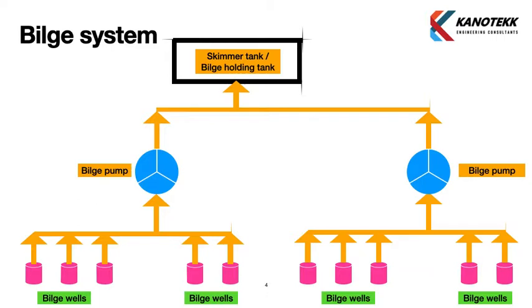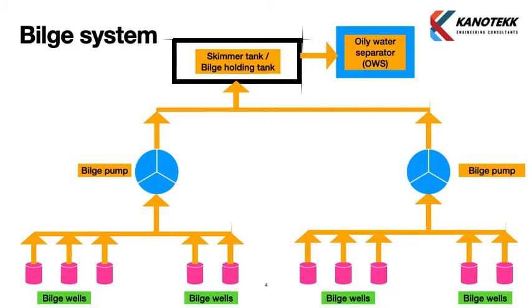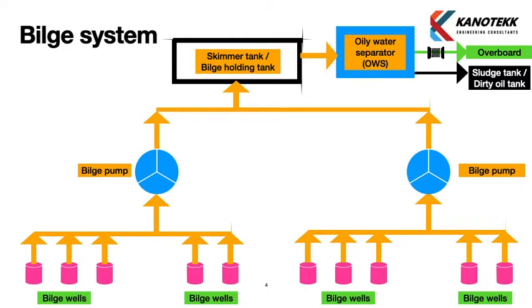The bilge holding tank stores the bilges, and the oily water separator takes suction from the bilge holding tank. The oily water separator separates oil and water, and the clean fluid is pumped overboard. The criteria is that the oil content in the clean separated fluid should be less than 15 ppm. The oil content monitor in the oily water separator measures the output and ensures only water meeting this criteria is pumped overboard. The remaining residue oil is kept in the sludge tank or dirty oil tank, which is eventually pumped to a supply vessel — it cannot be discharged overboard.